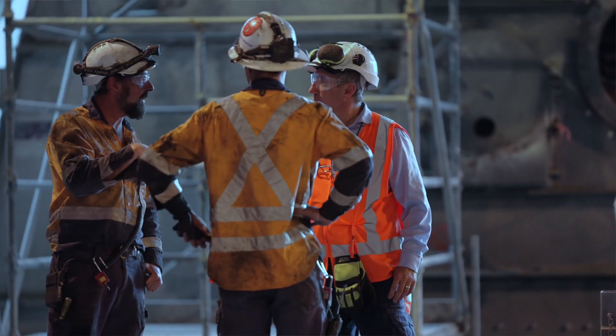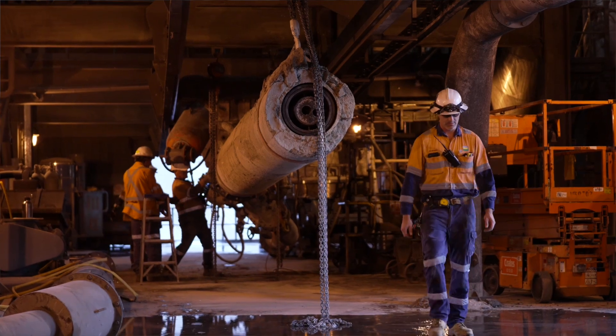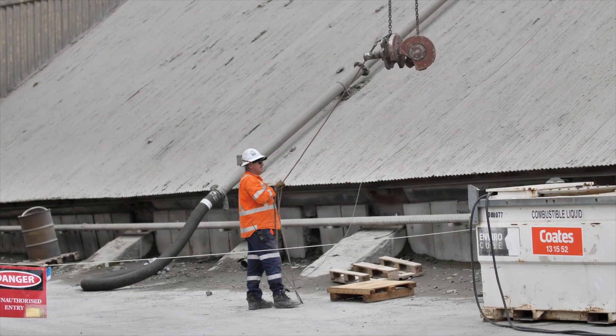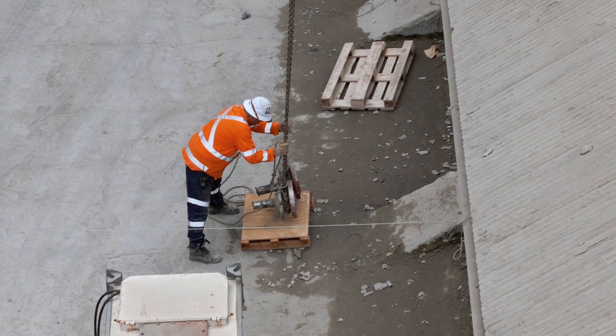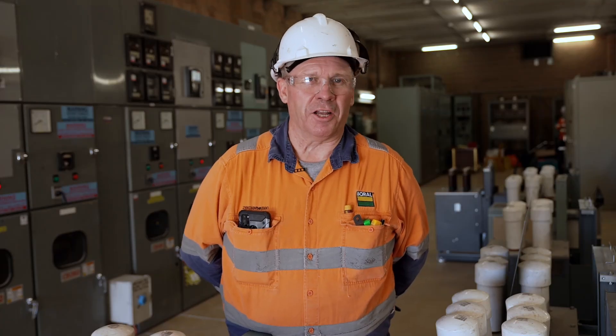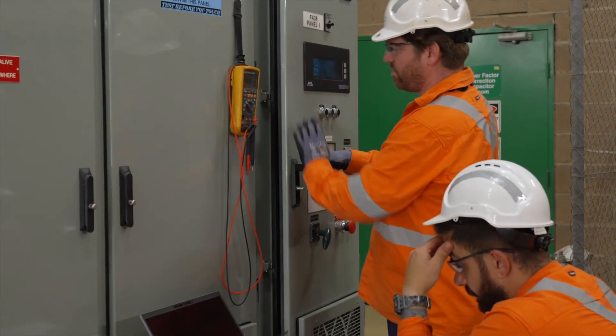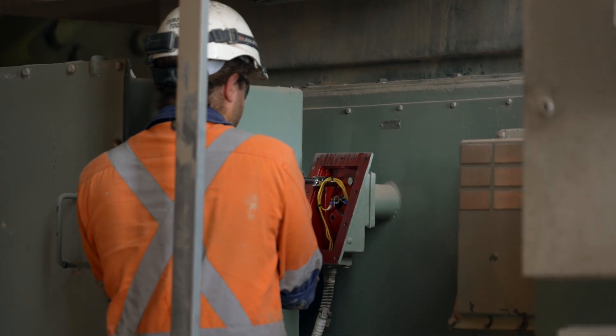On the mechanical and electrical side, equipment gets opened up, inspections are done on the internals, and once a problem is found we rectify or replace it. We have in the vicinity of 1,300 to 1,500 motors, isolators, and over 20 motor control centres that require maintenance throughout the whole shutdown.